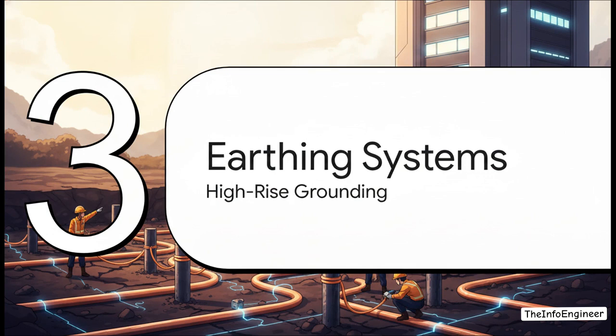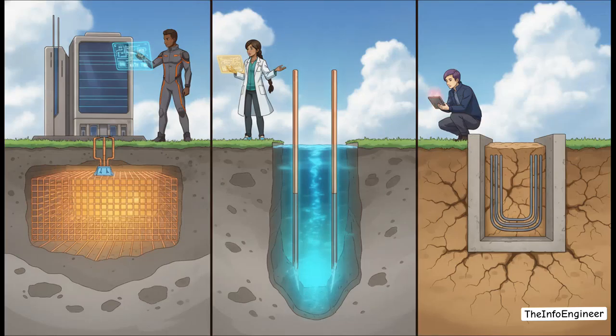Section 3. Designing earthing systems for high-rise and commercial builds. Depending on your soil resistivity test results, you've got a few options for grounding. For large commercial sites, you're usually deploying a massive bare copper grid under the building for uniform potential. Need to hit the water table? You drive copper-bonded steel vertical rods deep into the earth. But what if you're building in a bone-dry desert environment? That's where you deploy Ufer grounding.